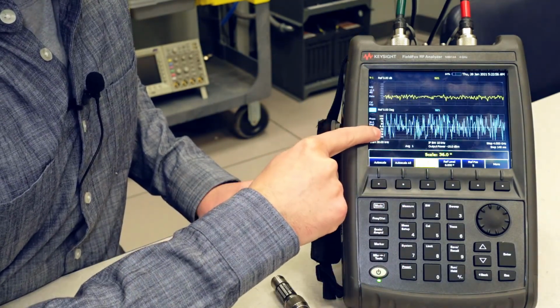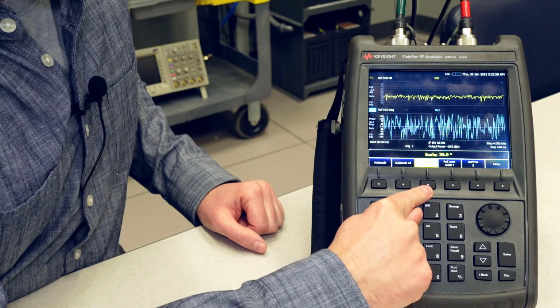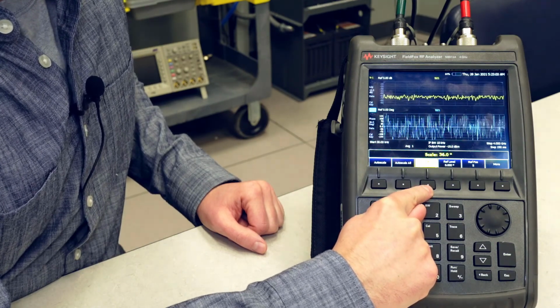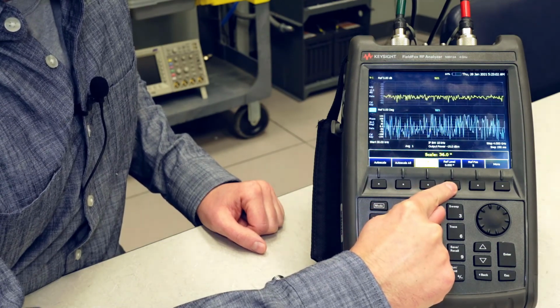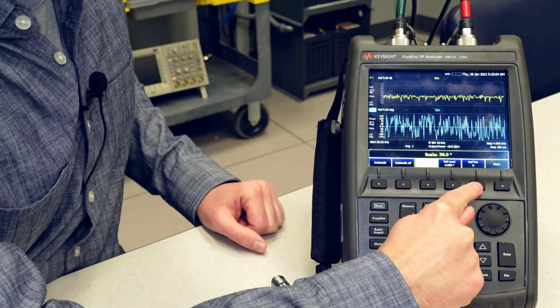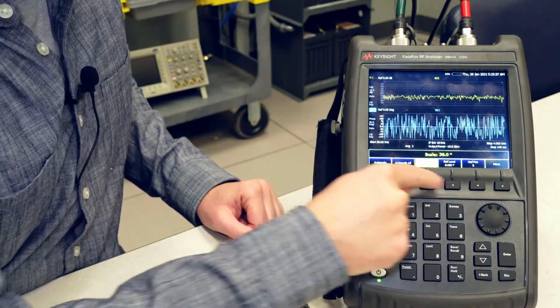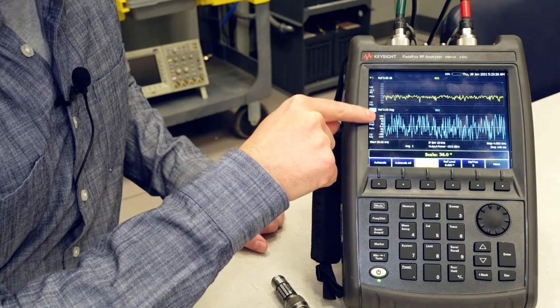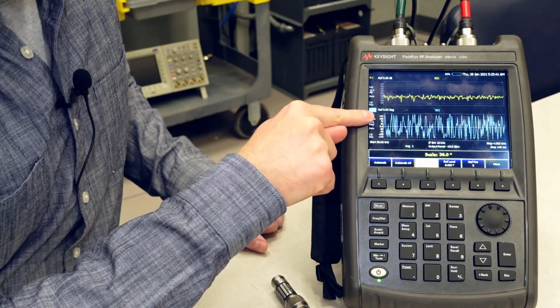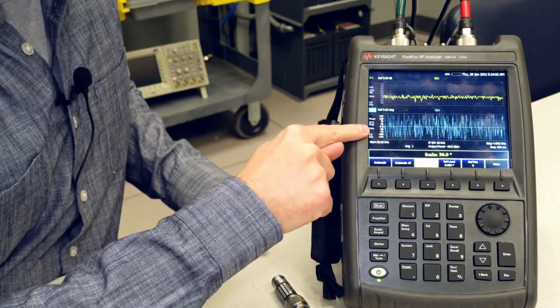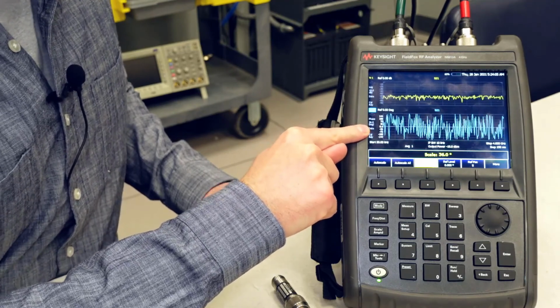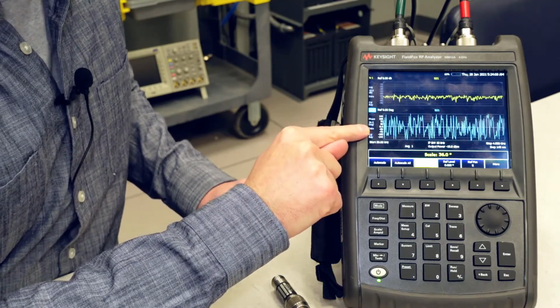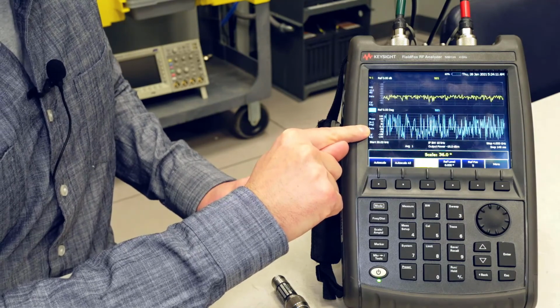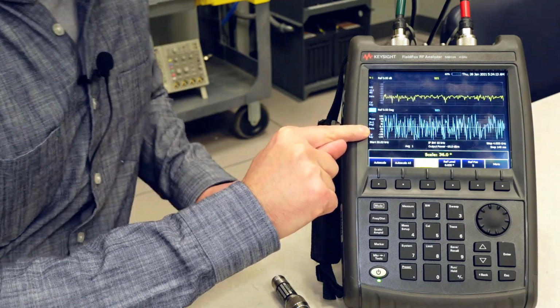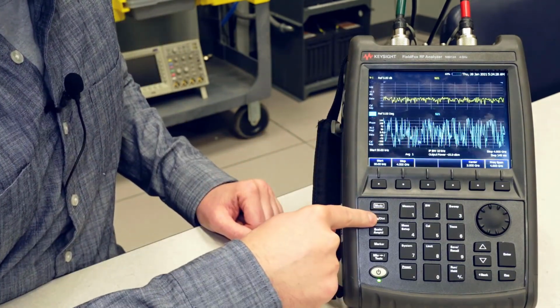Everything is already set here with a scale of 36 degrees per division and a reference level of 0 degrees with a reference position of 5. With all of these settings in here, this gives us a nice visual range of a full 360 degrees. This is pretty much the same convention that all vector network analyzers use, positive 180 to negative 180 for 360 degrees total. And the next thing we need to set up is frequency.